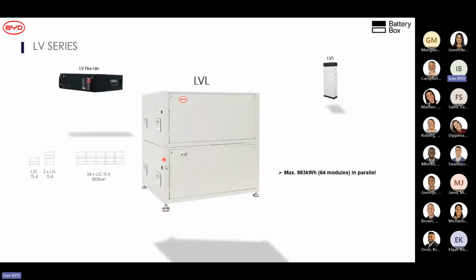So the LVL is very useful for everything from residential all the way to commercial systems. So you've got 1 battery module, 1 battery bank can do 15.4 kilowatt hours, and you can parallel those all the way up to 64 modules, which is 983 kilowatt hours. If you've got an SMA cluster system, you can have up to essentially 12 megawatt hours on a single system, because you can put essentially 1 megawatt hour per cluster, and you can have up to 12 clusters. So if you're looking for very large storage, that's also an option.